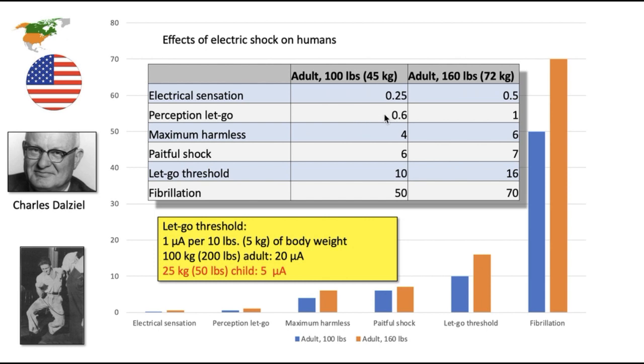Perception let go, basically your instinctual desire to let go or just step away from the thing shocking you, was 0.6 and 1 milliamp respectively. Maximum harmless barrier was 4 to 6. And coincidentally, that's the current value of a ground fault current allowed on the US-made GFCI devices.